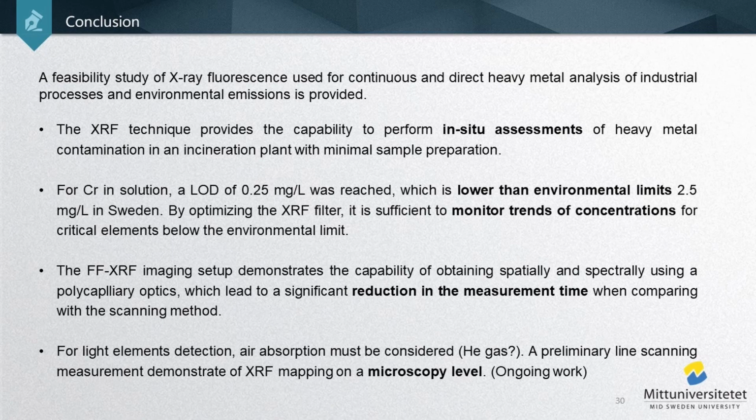For chromium in solution, a limit of detection of 0.25 milligram per liter was reached, which is lower than the environmental limit of 2.5 milligram per liter in Sweden. By optimizing the XRF filter, it is sufficient to monitor the concentrations of critical elements below the environmental limit.